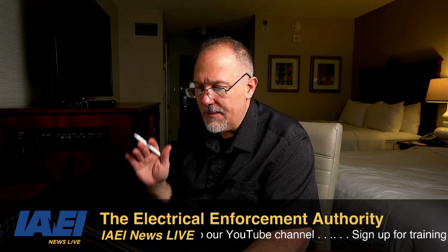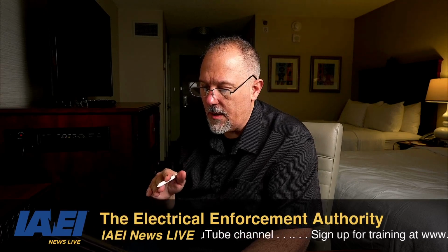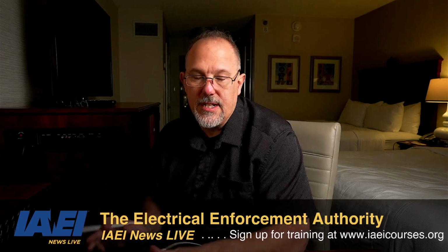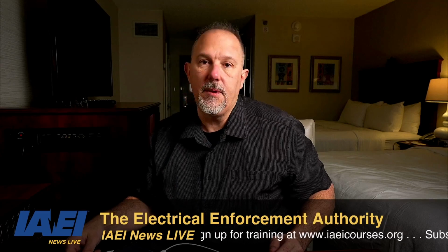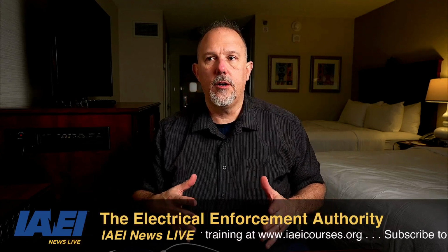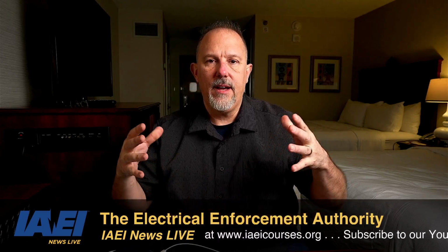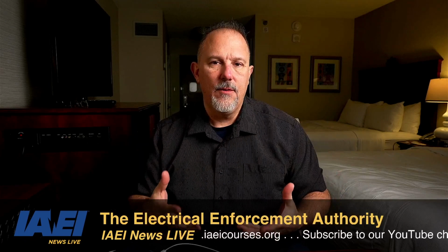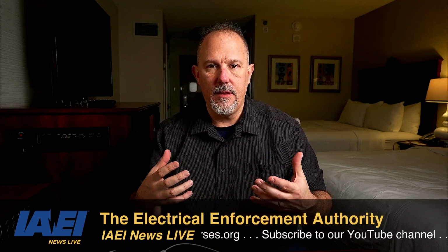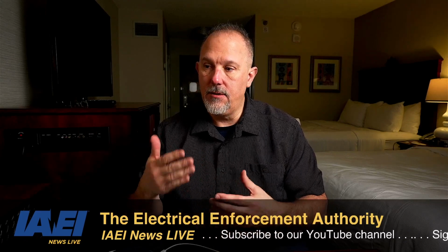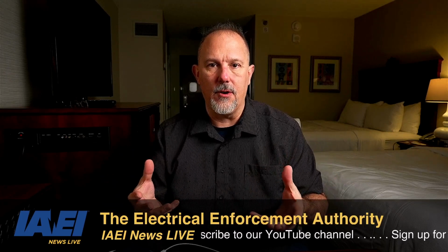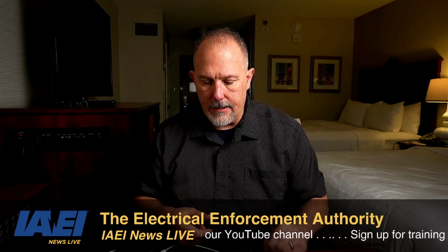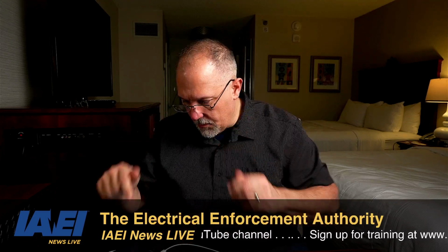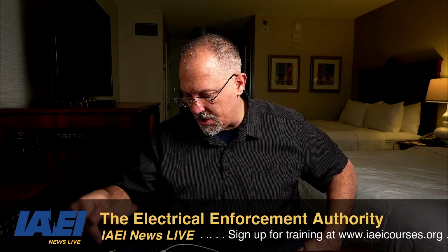Location: generators shall be of a type suitable for the locations in which they are installed. They shall also meet the requirements of motors in 430.14. Now, if we look at 430.14, you have to be mindful. If you have, say, a diesel generator or a gasoline generator, the fuel is very important, and you have to think about the ventilation and the contents of the fuel that are basically turning the generator, the prime mover, so to speak. In 430.14, they talk about motors shall be located so that adequate ventilation is provided so that maintenance, such as lubrication of bearings and replacing of brushes, can be readily accomplished.